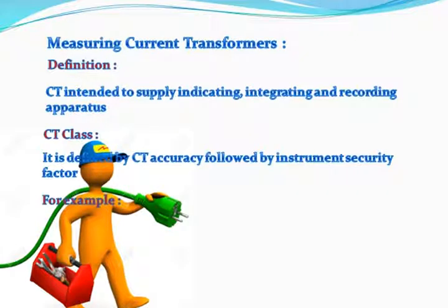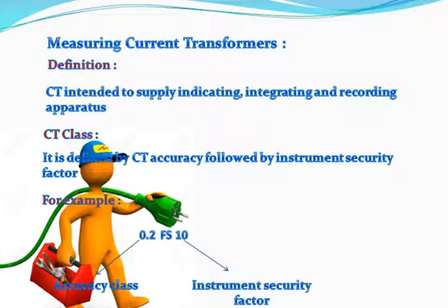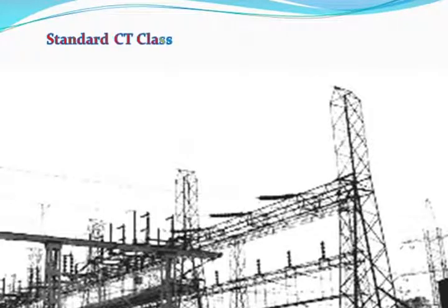For example, consider 0.2 FS10, where 0.2 is the accuracy class and 10 is the instrument security factor. 0.2 FS10 is a special purpose measuring CT. As per IEC, the standard classes of CT are 0.1, 0.2, 0.2S, 0.5, 0.5S, 1, and 3.